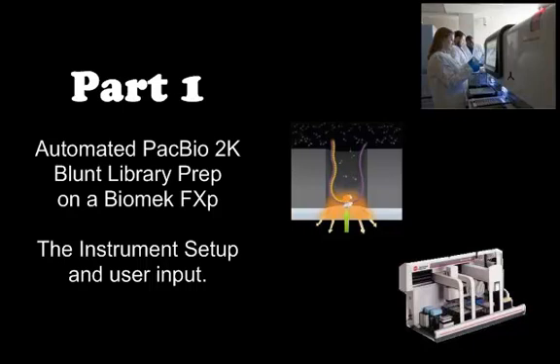We actually run this on a Biomek FXP. It's a dual bridge unit, has 96 head on one side, span 8 on the other. I don't really see any reason why you couldn't run this on a standard FX. One of the major differences between an FX and an FXP, the hardware was upgraded to give you more accurate positioning on the span 8. So you may need to add more extra samples so you have a little extra volume. But if the system is set up well, I don't think you'll have a problem. But all the testing was done on an FXP.